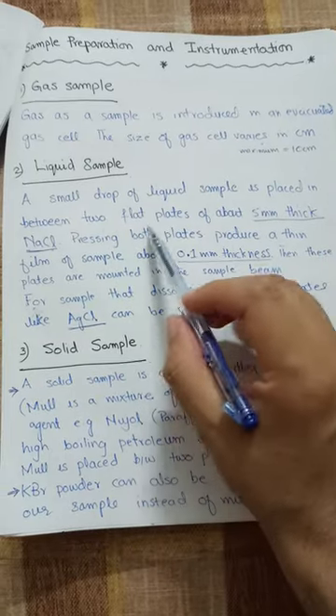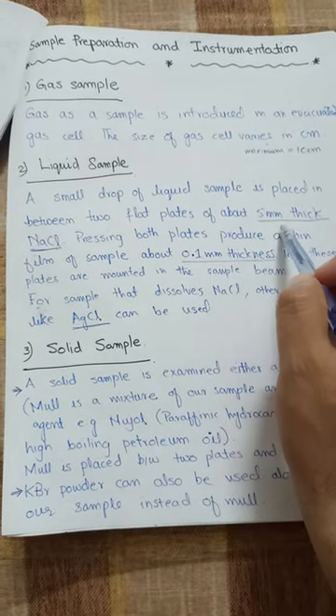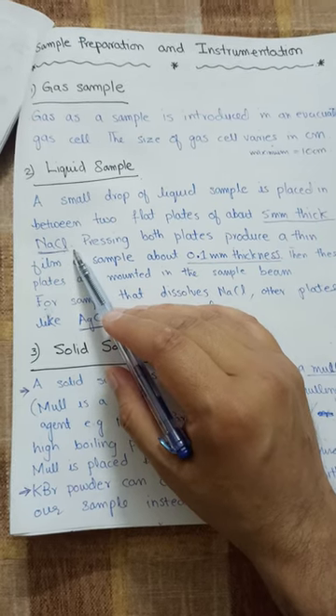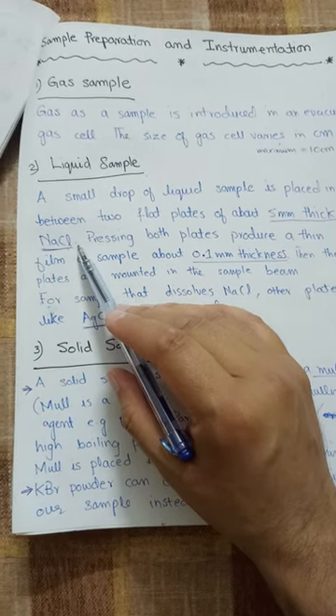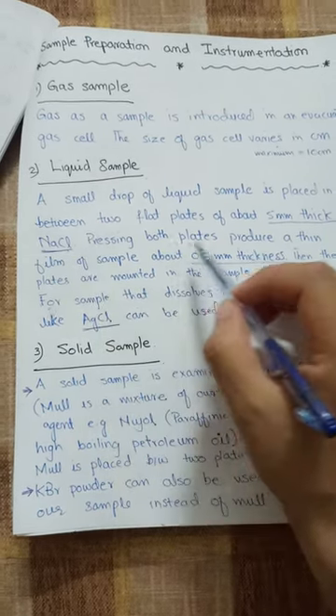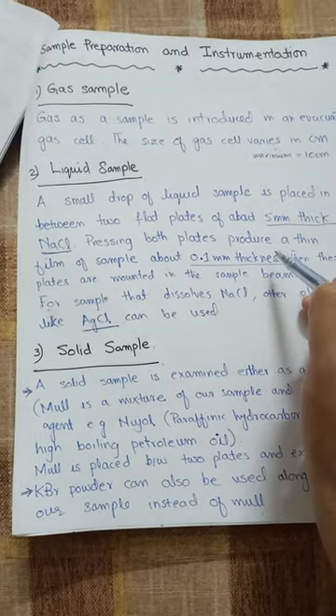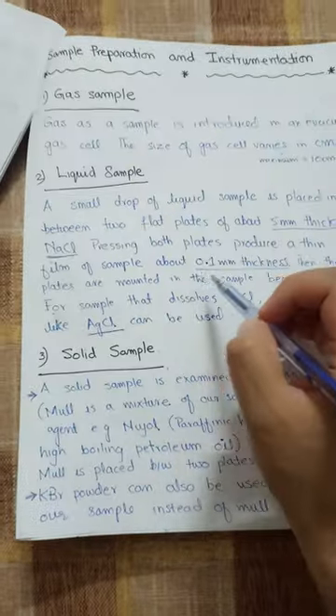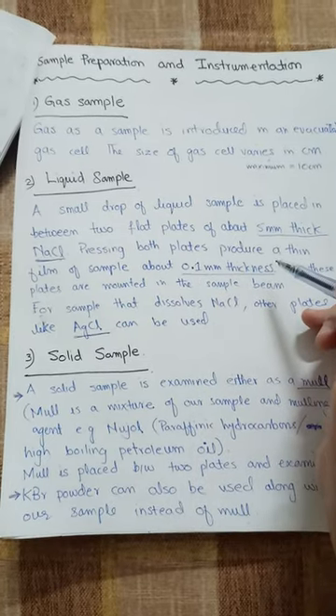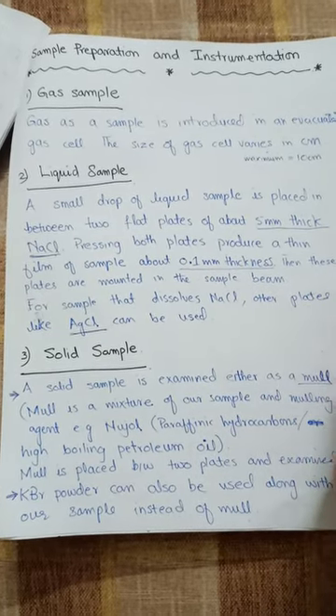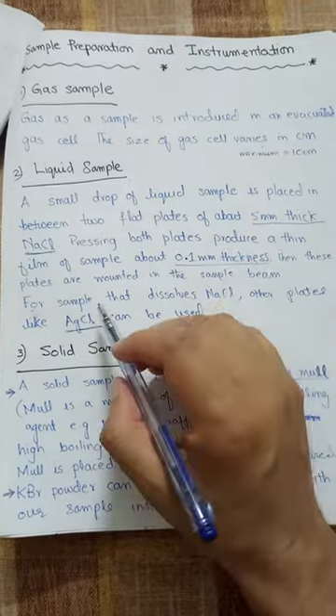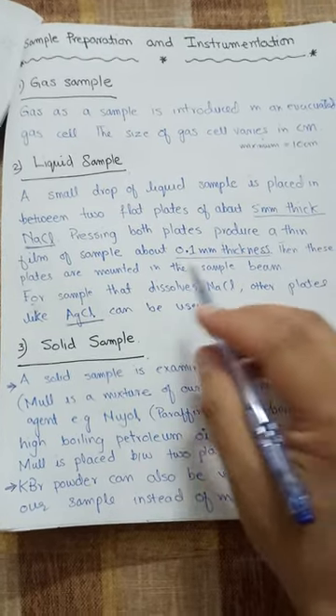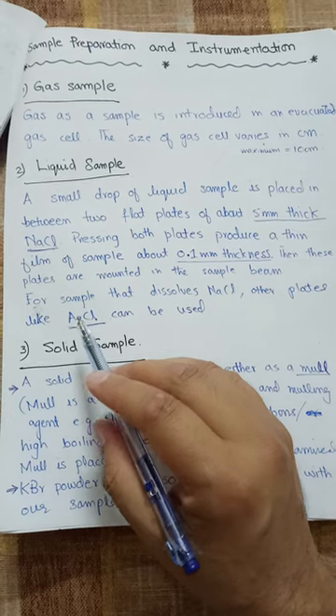For a liquid sample, a small drop of the liquid sample is placed between two flat plates of about 5 millimeter thickness made of NaCl (sodium chloride). Pressing both plates produces a thin film of sample which is about 0.1 millimeter in thickness. These plates are then mounted in the sample cell where the beam passes.